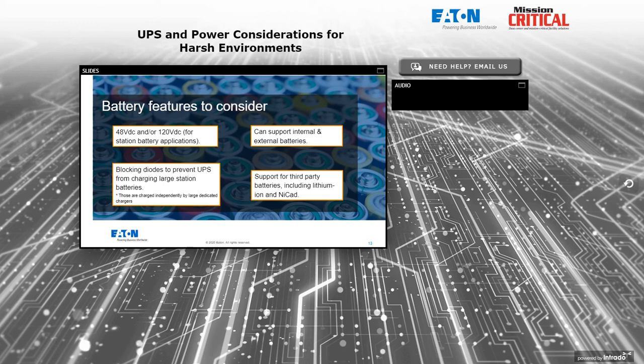So the UPS system should be designed to support both its own internal batteries in the size range and external batteries from a multitude of vendors and a multitude of types. Maybe NiCad batteries are supported, lithium-ion batteries, other chemistries. It's the kind of thing you can check out with the UPS vendor, and they can respond with information on what types of chemistries are acceptable.